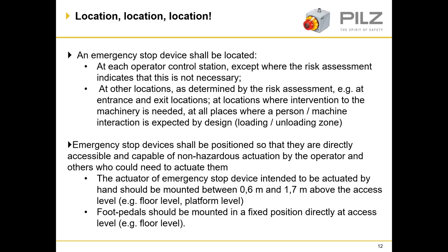The actuator of an emergency stop device intended to be actuated by hand should be mounted between 0.6 metres and 1.7 metres above the access level — for example the floor level or a platform level. Foot pedals should be mounted in a fixed position directly at access level. The positioning of emergency stops shouldn't introduce further hazards by potentially having to reach over other hazards to reach them, and foot pedals should be fixed to the floor to stop them moving around and potentially creating tripping hazards.